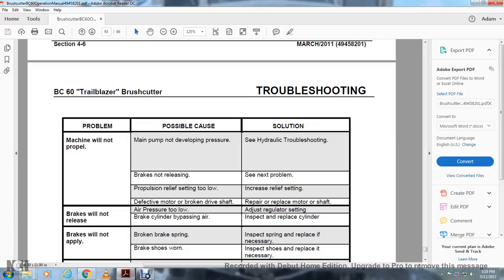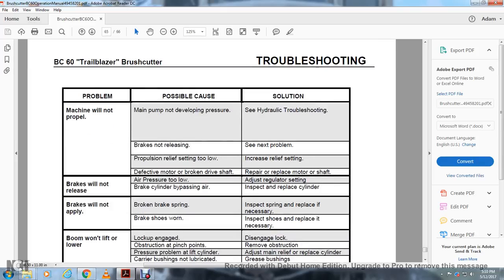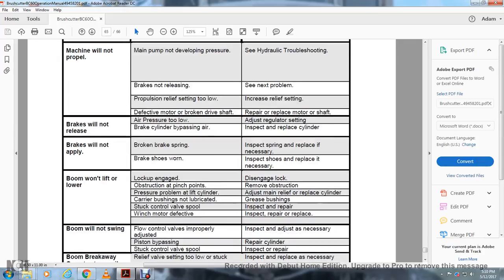Brakes will not release. Air pressure is too low: adjust the regulator setting. Brake cylinder bypassing air: inspect and replace the cylinder. Broken brake spring: inspect the spring and replace if necessary. Brake shoes worn: inspect the shoes and replace if necessary.